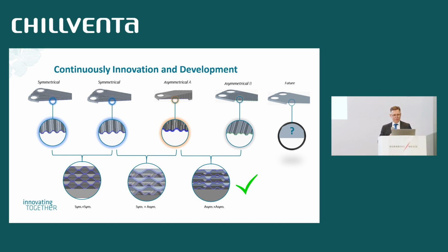However, within refrigeration, we have gone further to asymmetric plate patterns. Asymmetric means you have tighter channels on the refrigerant side and larger channels on the water side, to decrease the pressure drop on the water side and also decrease the charge of refrigerant on the refrigerant side.